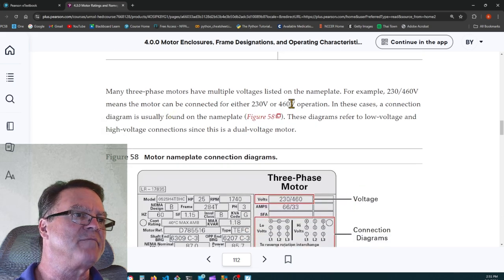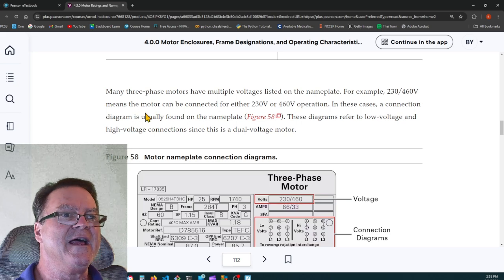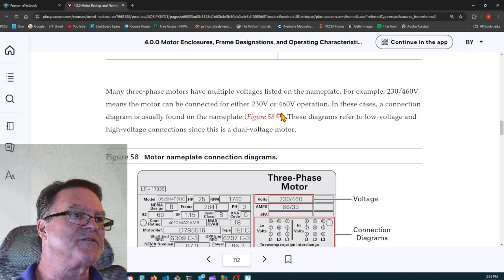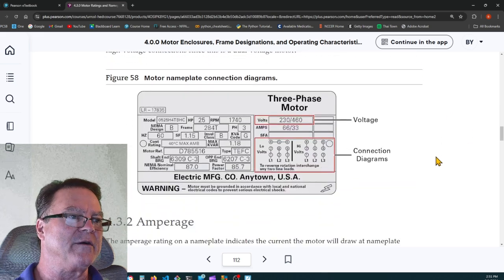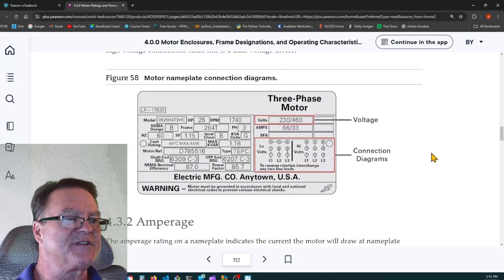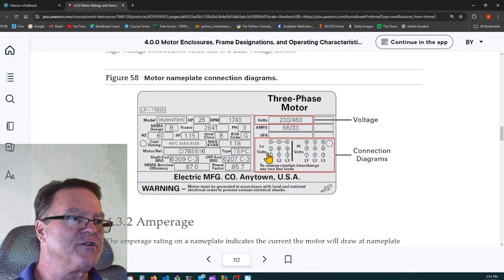Many three-phase motors have multiple voltages listed on the nameplate, for example, 230, 460. It means the motor can be connected for either 230 volts or 460 volts. You have to rewire it. You can't just use the same hookup. If you're going to do it in low voltage, you want to operate this at 230 volts, it's going to draw 66 amps. You hook up 1 and 7.